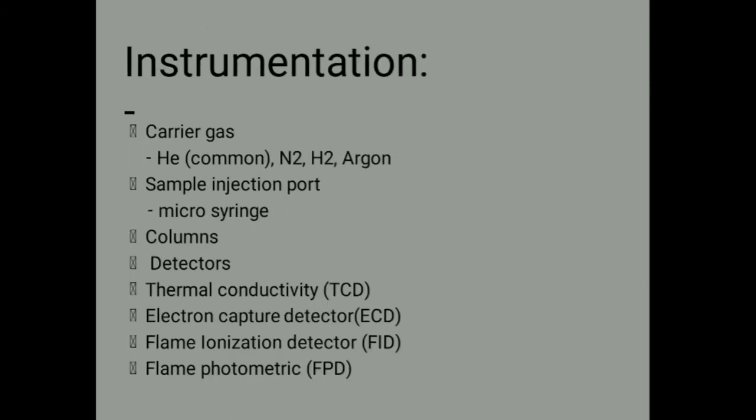Talking about the instrumentation. First, we have a carrier gas; commonly we use helium and argon. Next, we have the sample injector port, then the column and detector. There are four types of detectors: thermal conductivity detector (TCD), electron capture detectors (ECD), flame ionization detectors (FID), and flame photometry detector (FPD).